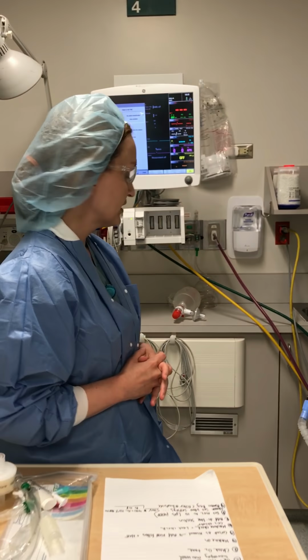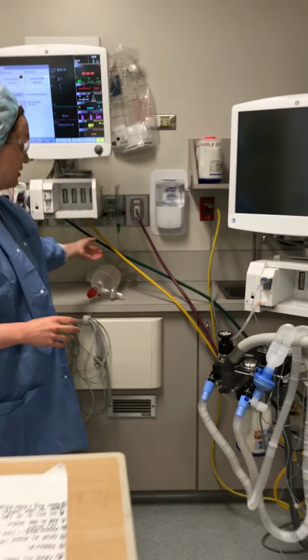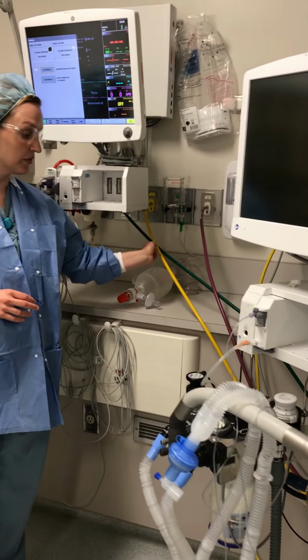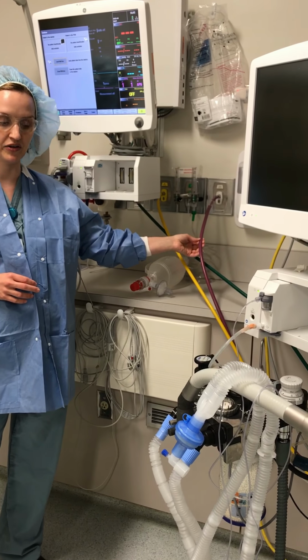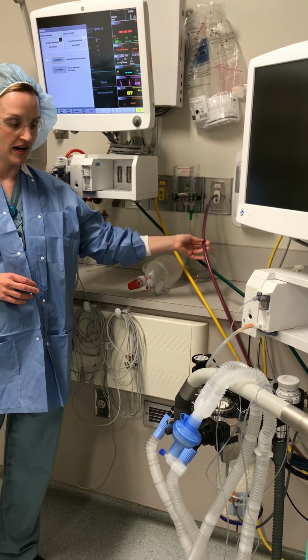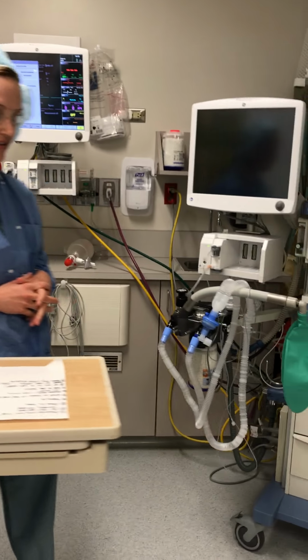We have our oxygen and our air tubing plugged into the wall as well. And then we were actually able to scavenge in our PACU, which may be different for other hospitals. But all of those should be plugged into the wall. And then lastly, and very importantly, we need to check our oxygen tank in case of pipeline failure, so that we have a way for the ventilator to deliver oxygen to the patient.